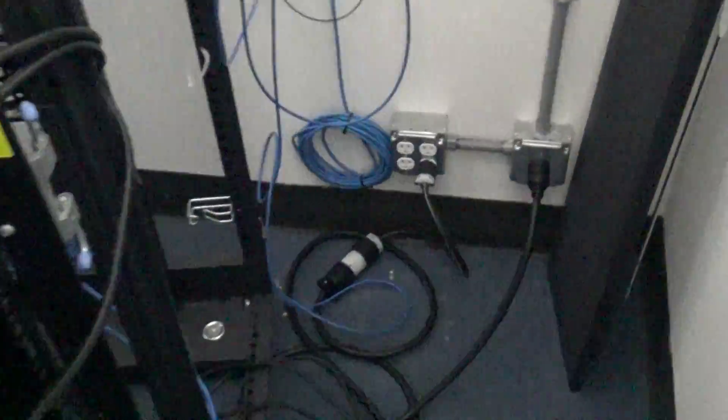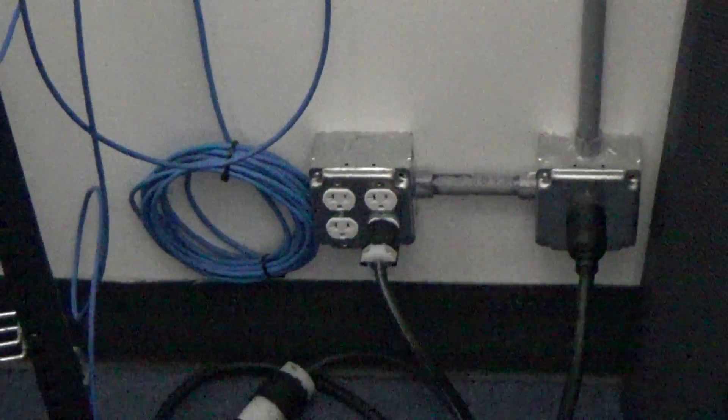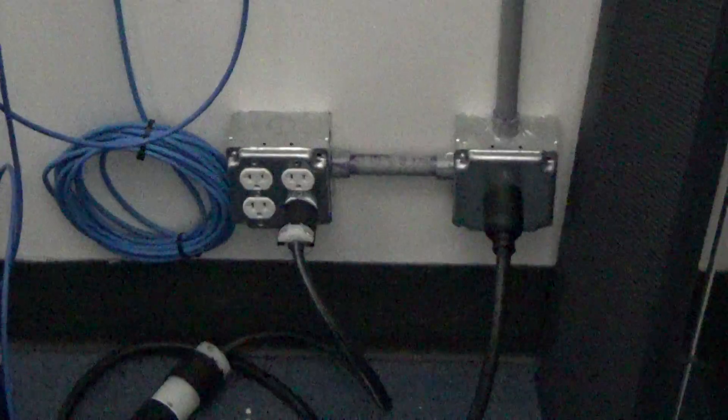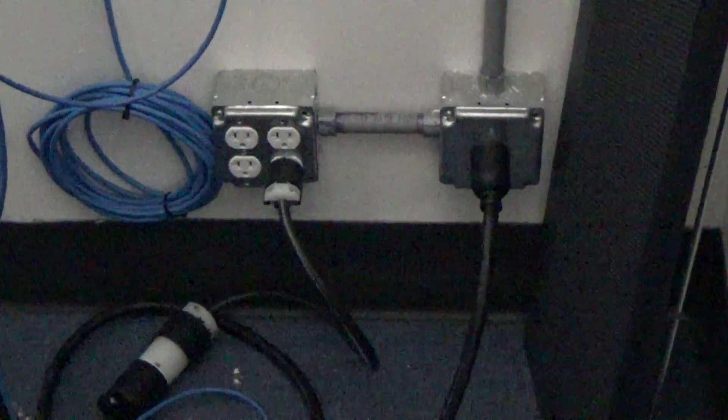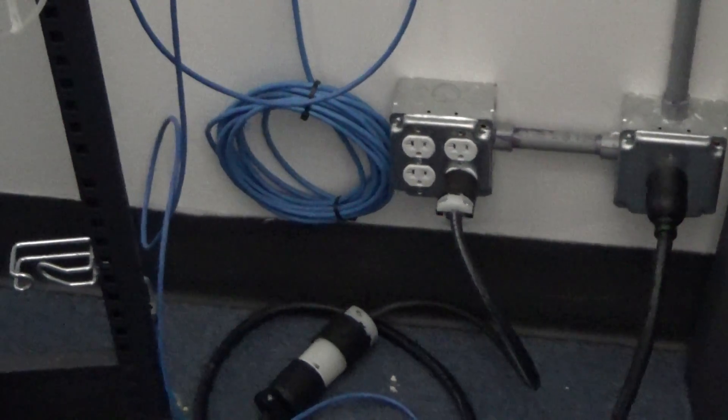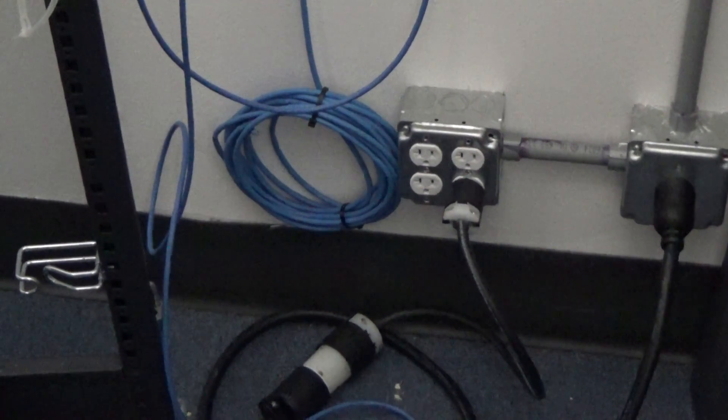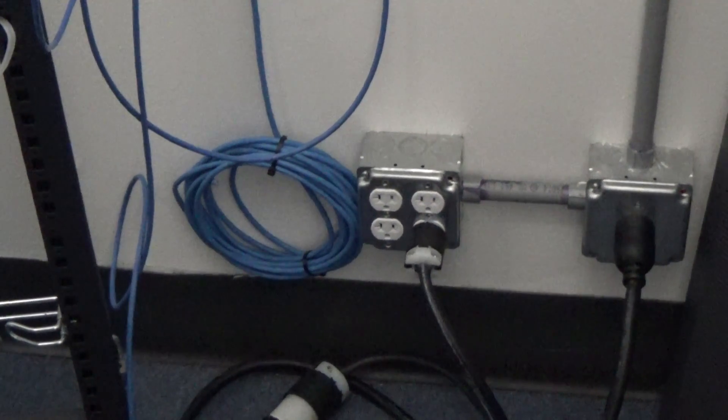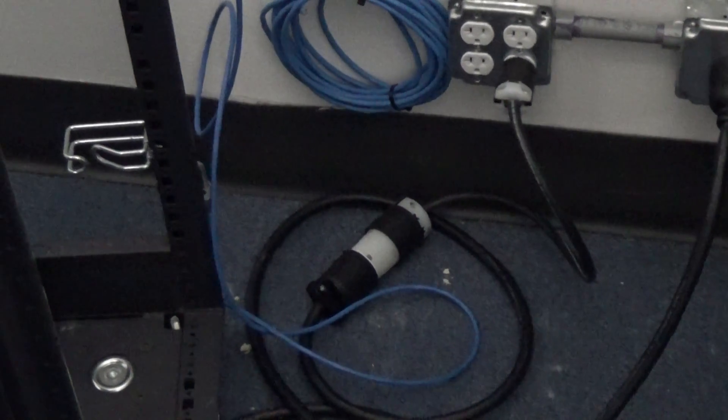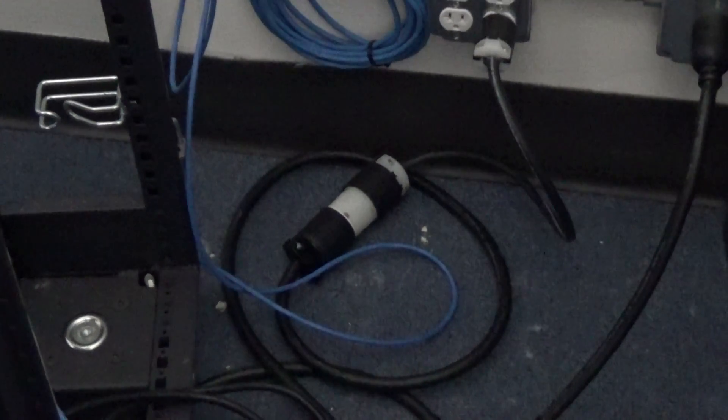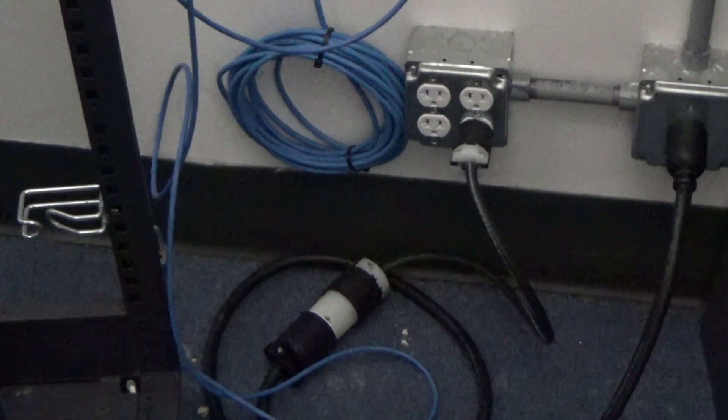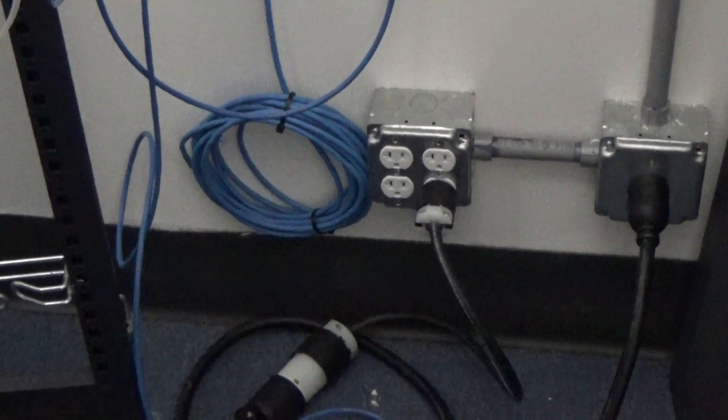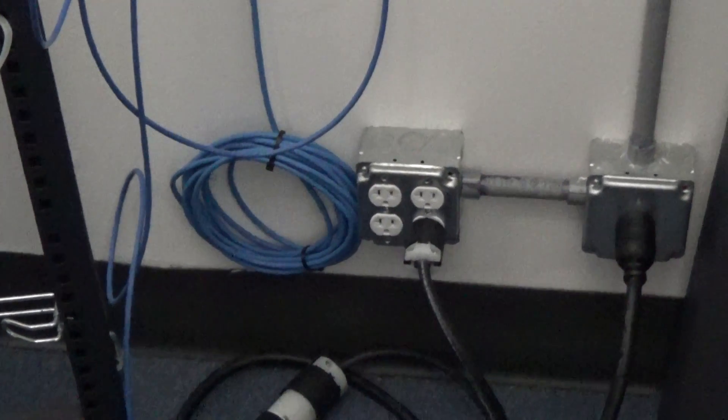I've also got over here these outlets. I think I've shown in another video, but there's actually two dedicated circuits feeding these two boxes. The box on the right is for a 30 amp twist lock that's directly going to one of the UPSs. And the box on the left is what I was using before. That's why it has just those 15 and 20 amp outlets in there, because those just have UPSs and some PDUs plugged into it. I've got this camper adapter converting that 30 amp twist lock into a 15 amp plug that's going in there. But that UPS only has like 5 amps on it right now, so that's safe. That's not a problem, but I am going to probably pull all of those outlets out and put just a 30 amp twist lock there in its place. That way the two UPSs will both be on their own dedicated circuits.